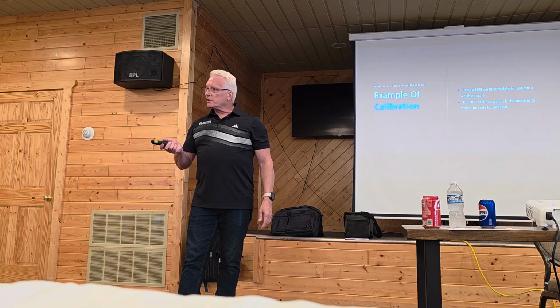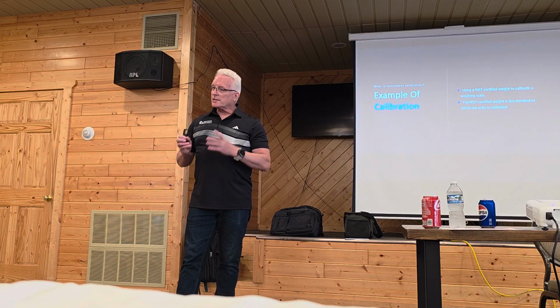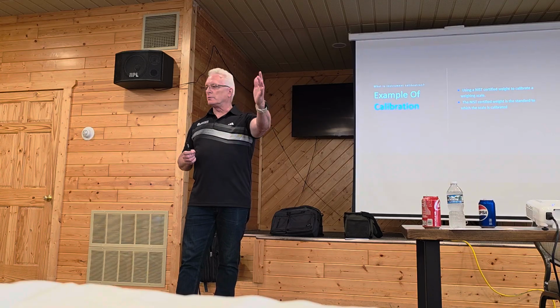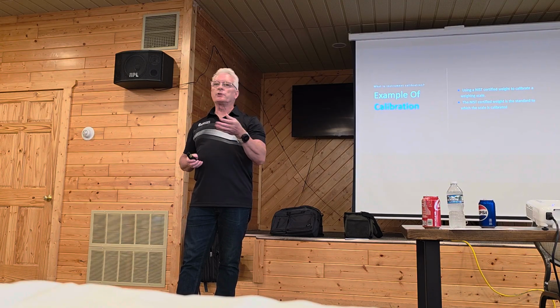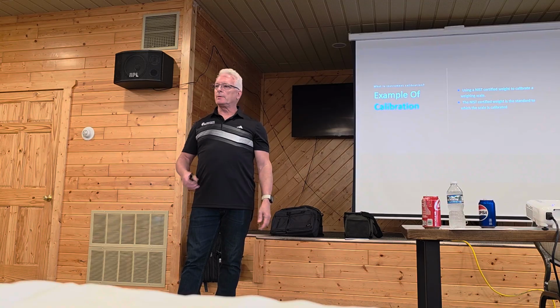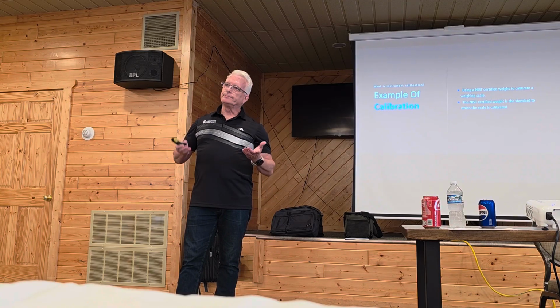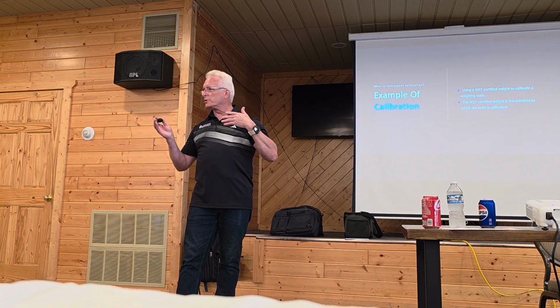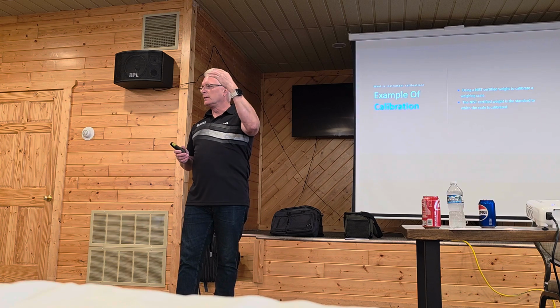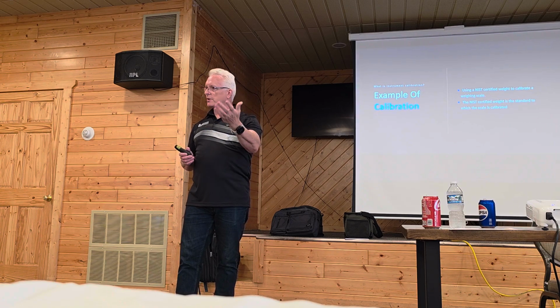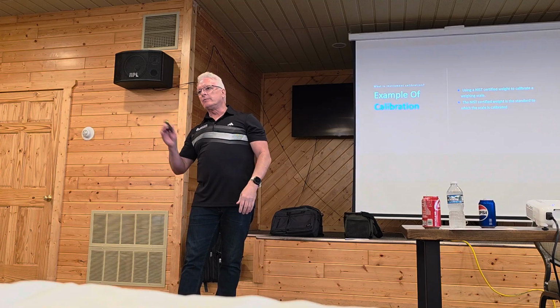Then we get to mag meters, and mag meters, you used to have to take them out and send them in, and they put measured water through them. That's a true calibration. So you'll hear people say, well, you can't calibrate a mag meter. Depends on what your definition of calibration is. If you go by the dictionary, yes, you can, because it's anytime you're verifying and checking it. But they'll say, well, it's a verification.